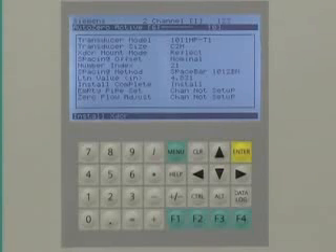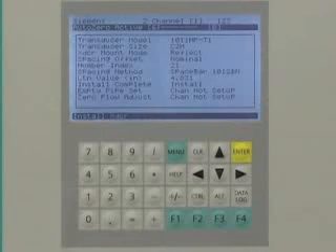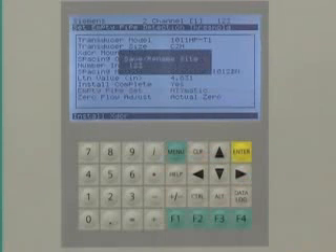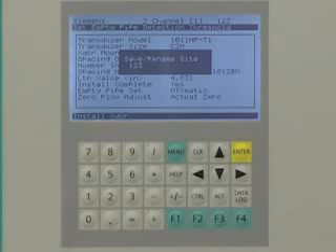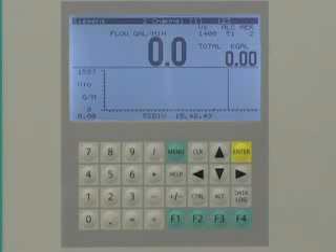The Sitrans FUS-1010 will automatically begin the Auto-0 routine. The Auto-0 routine is only for applications where the sensors are mounted in reflect mode. When the Auto-0 is complete, the flow meter is ready to measure flow. Press the menu key and the FUS-1010 will prompt you to save the site data, providing a backup for future use or recovery. Press the right arrow and enter key to save. The display will now show the instantaneous flow rate and totalized flow values.